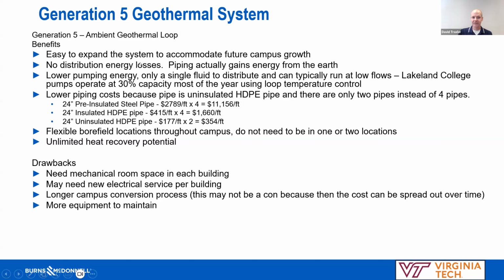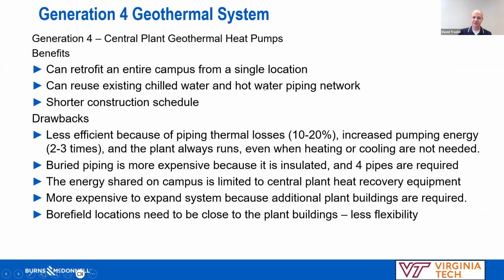So there are some definite and huge advantages, though. The water in the pipes that are circulating is basically a gigantic storage system for your energy that you get for basically free. And your horizontal piping also is dissipating heat to the ground, which is an advantage. Where with your insulated systems, you never really want to exchange any energy with the ground around you. With your ambient loop system, any ground exchange is bonus. So that's a real advantage of those. If you're looking at a central plant system, the expediency is the main advantage. You can retrofit an entire campus from one location, especially if you already have a hot water network on your campus. You can reuse existing chilled water and hot water piping if it exists, and you have a much shorter construction schedule.